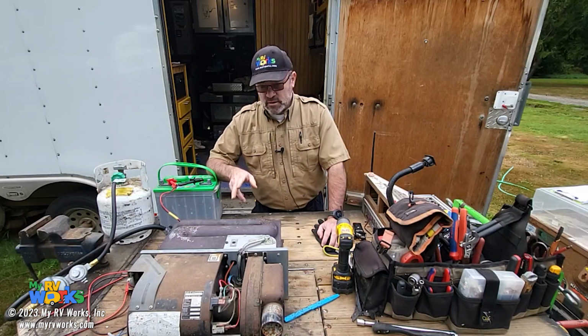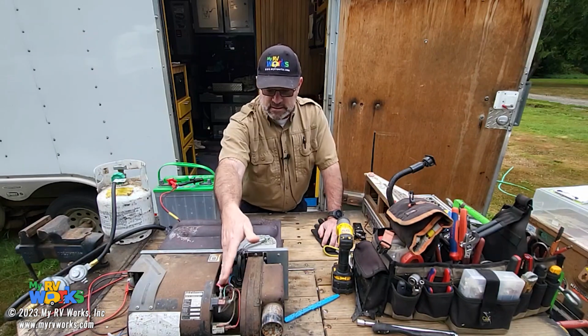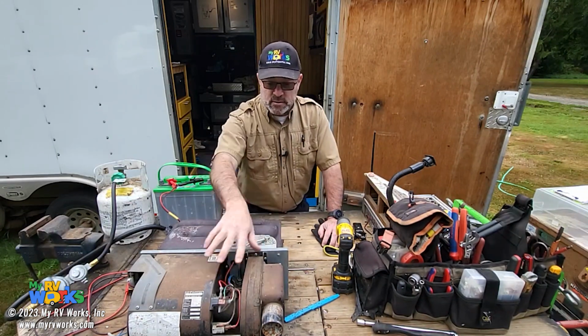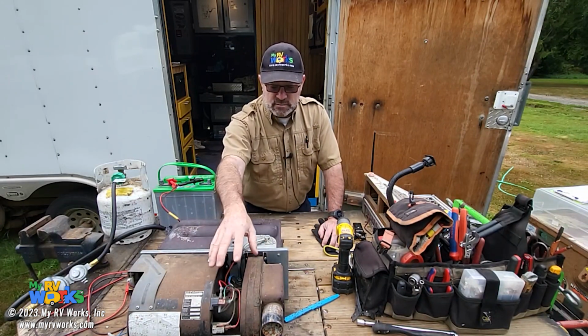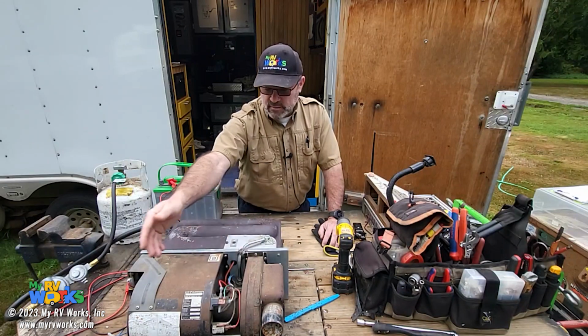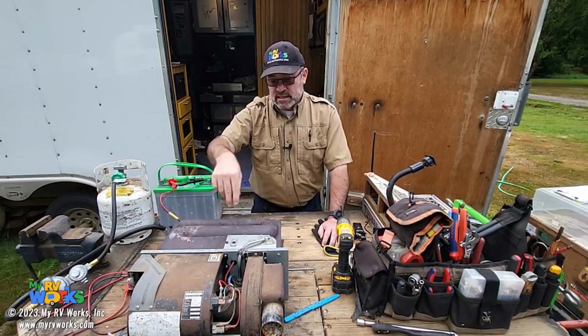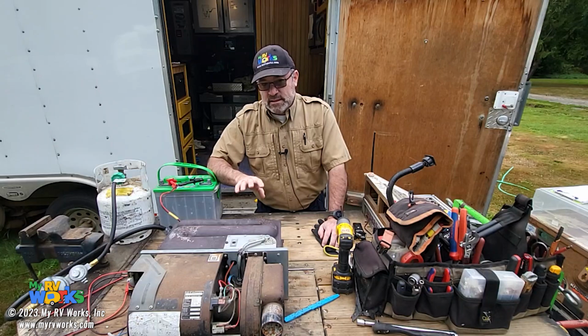The first issue is the motor is squealing, so we're going to be replacing the motor. I have a couple of furnace videos where we're replacing the motor. This one's down deep inside and you have to take quite a few parts apart to get to the motor, so you can follow along on how I do that. I'll go ahead and let you listen to it. It's squealing. But the second thing this furnace is doing is a very intermittent issue.